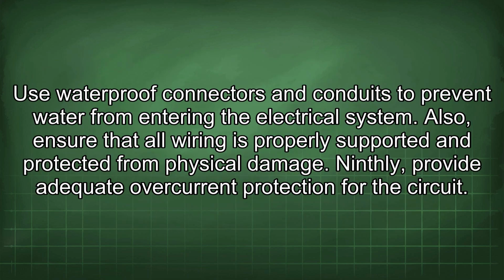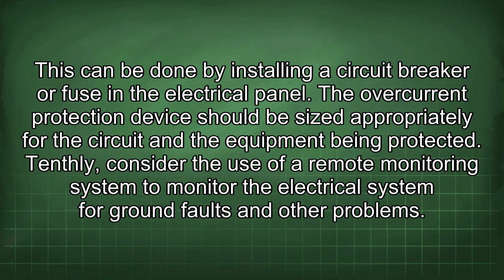Use waterproof connectors and conduits to prevent water from entering the electrical system. Also, ensure that all wiring is properly supported and protected from physical damage. Ninthly, provide adequate overcurrent protection for the circuit. This can be done by installing a circuit breaker or fuse in the electrical panel. The overcurrent protection device should be sized appropriately for the circuit and the equipment being protected.